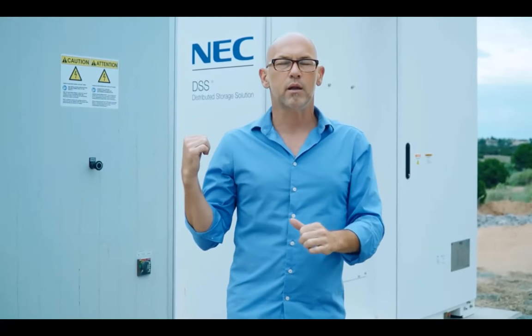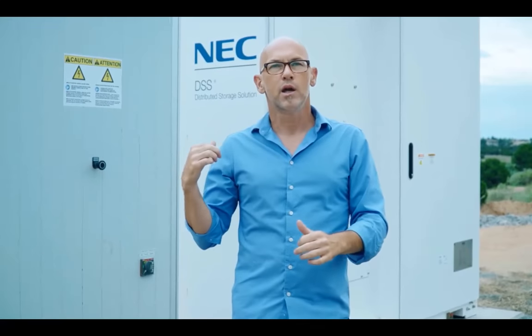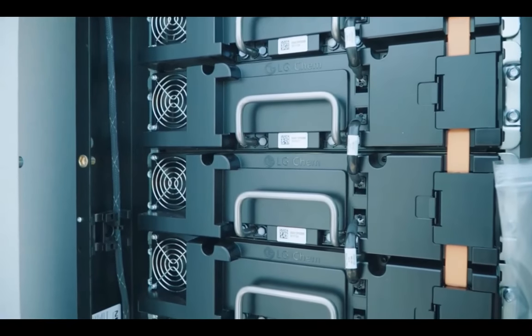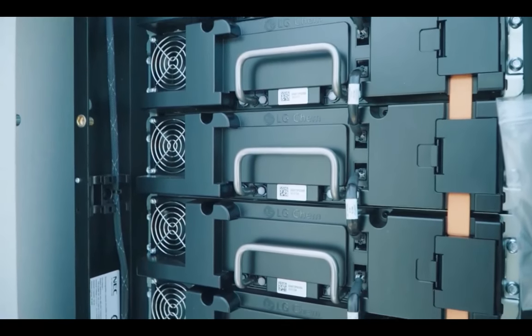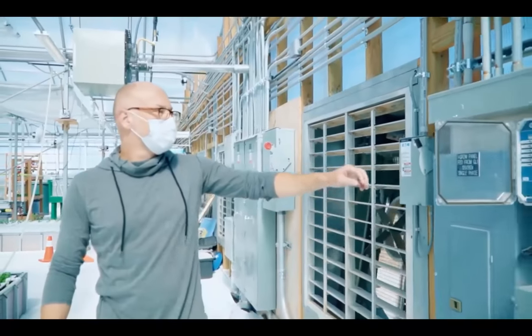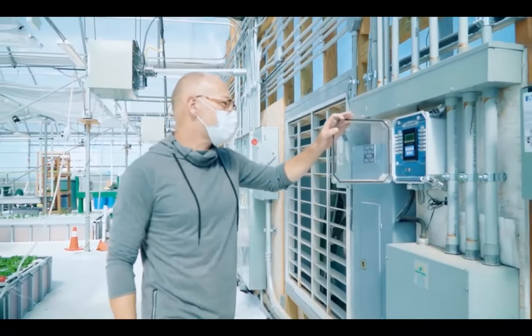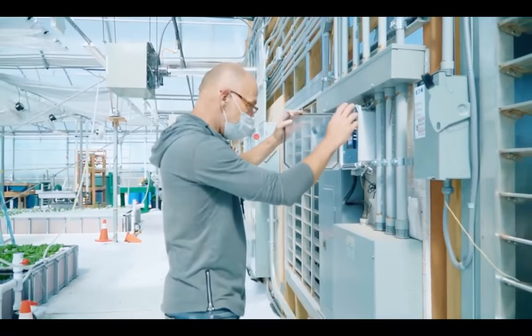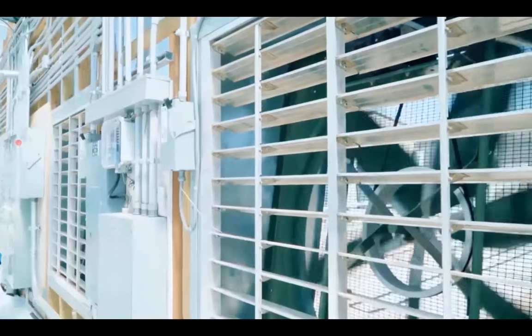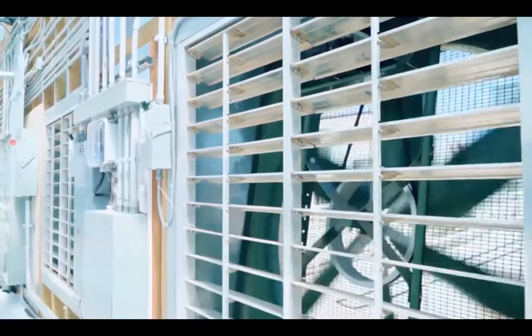This is 100 kilowatts — let me do a little quick math — it's about $23 a kilowatt times 100. So if we can discharge this at full capacity while the peak is going on and shave the peak for the school, that's a couple of thousand dollars that comes off the bill every month just for turning on for the right 5 minutes.